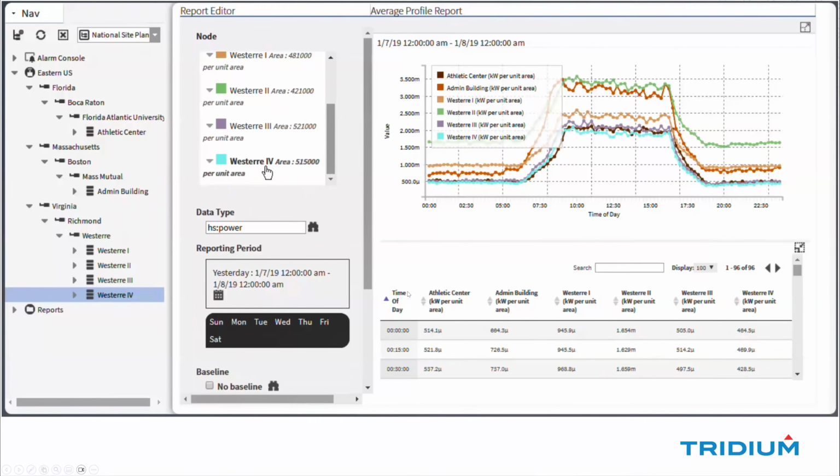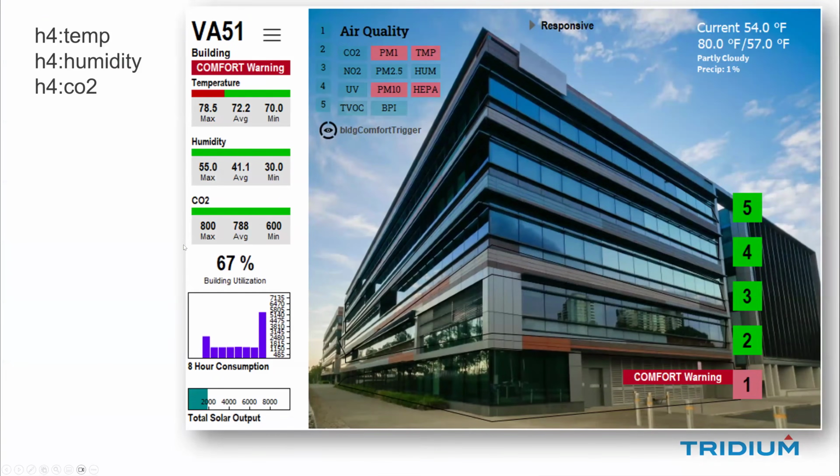Analytics relies on tags. This is very important for looking for things inside the station, and the tags and the relationships go a long way to help you find that. So I don't look for points, I look for tags. If I go after the temp sensor in this building and look at all of the tags inside the building, I will find 75 sensors for temperature. I can look at those as a group just by that tag.